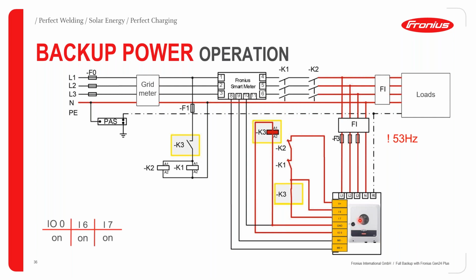Now, once the inverter sees this, it raises its output frequency, or AC frequency, to 53 Hz, thereby enabling it to function in an isolated mode. That is why, as Mo mentioned earlier, even if you have an AC coupled setup with the Gen24 inverter, it isolates the Snap inverter and functions in isolation because of this increase in frequency.